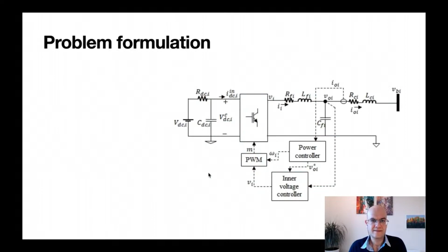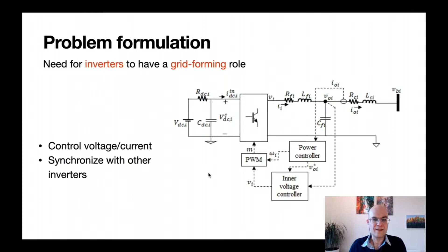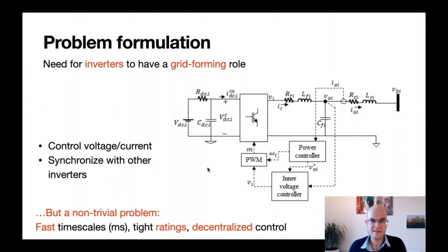Now, in an inverter-based grid, inverters need to also have a grid-forming role, meaning that they need to control the voltage and current, and also synchronize with other inverters. This is a non-trivial problem, as mentioned before, due to the fast timescales involved, and also the tight ratings of the converters, and the fact that these control policies need to be decentralized, since the fast timescales involved imply that a centralized implementation would not be practically feasible.